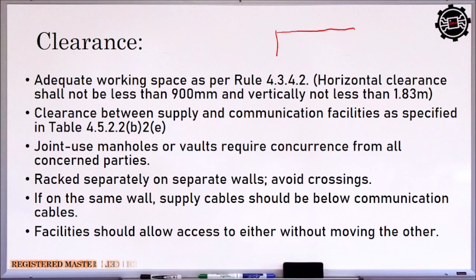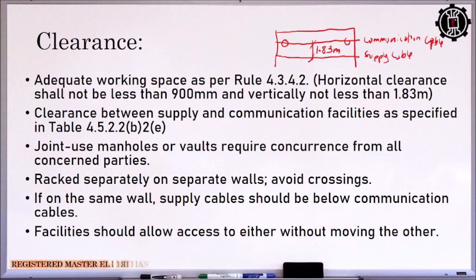Facilities should allow access to either without moving the other. So this means if we are going to troubleshoot this communication cable, we could troubleshoot it or cut this part of the ducting without hindering or damaging the supply cable below, or without moving it, so that we would not have to pull out the supply cable as well. Okay, so this is our clearance. I hope it is clear.